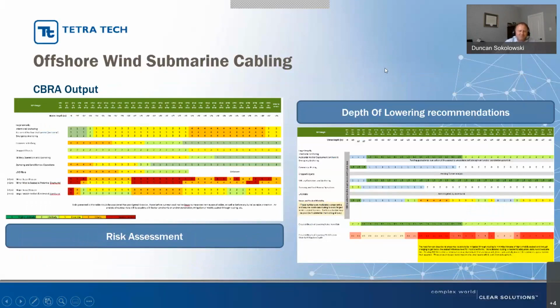The output of a CBRA is a recommended depth. On the left is a risk assessment, an amalgamation of all the risks along every section of the cable, almost on a meter by meter basis. Out of that you make depth of lowering recommendations, which lower the risk to something acceptable to the cable owner, the permitting authorities, and the electricity authorities buying the power.